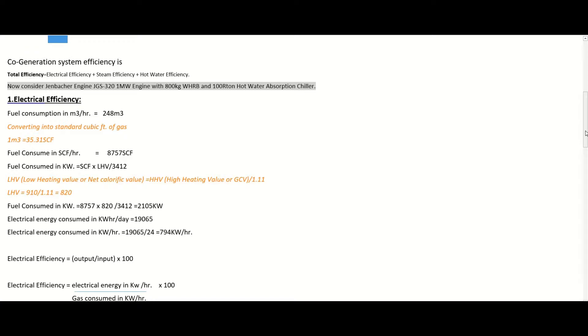First, let's talk about electrical efficiency. For the JGS 320 engine of 1 megawatt capacity, when it runs at 80 percent efficiency, its fuel consumption per hour is 248 cubic meters — you can also verify this from its catalog. Now, first convert this fuel consumption to standard cubic feet. Since one cubic meter equals 35.31 standard cubic feet, multiplying by 248 gives us a fuel consumption of 8,757 standard cubic feet per hour.